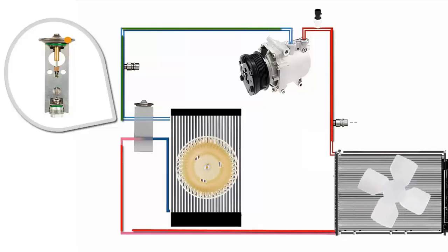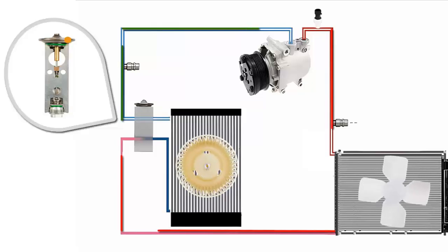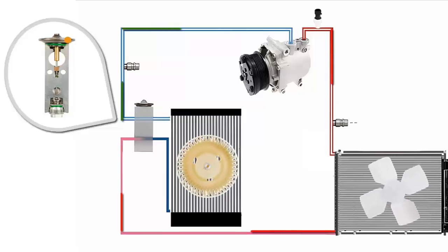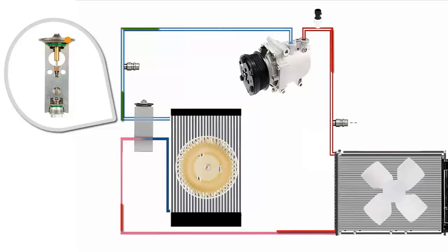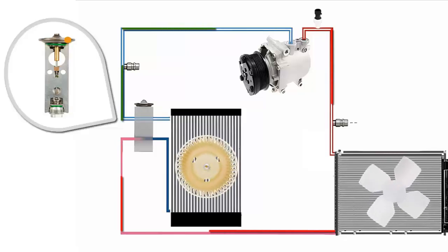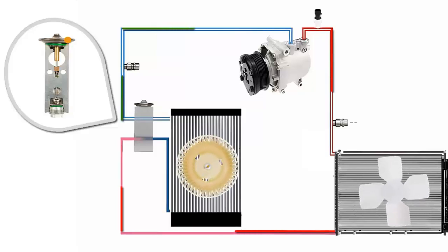6. After confirming that the system is clean, reassemble it, ensuring the equipment is off. Check for leaks by charging with nitrogen at 200 pounds per square inch, allowing the charge to sit for several minutes, and confirming the pressure holds, which indicates no leaks.